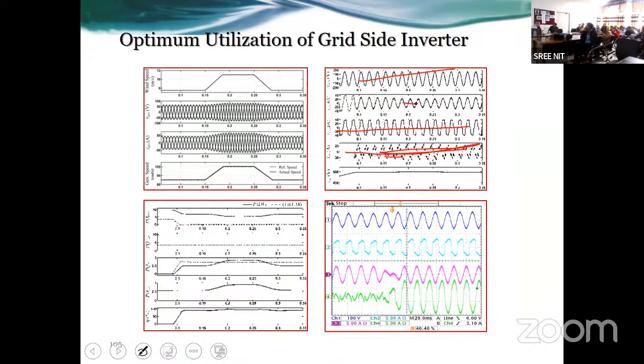And this is the experimental result, this is the load current profile. When it is generating less, the grid is supplying some power actually, but the phase reversal takes place when it is generating more than the load demand. So the grid current is now fed in the reverse direction. You see here, positive peak, negative peak of the voltage, and positive peak of the grid current. That means phase reversal, means power is flowing back to the grid.